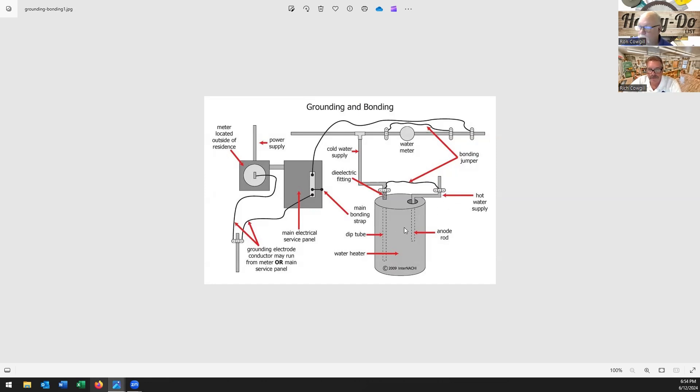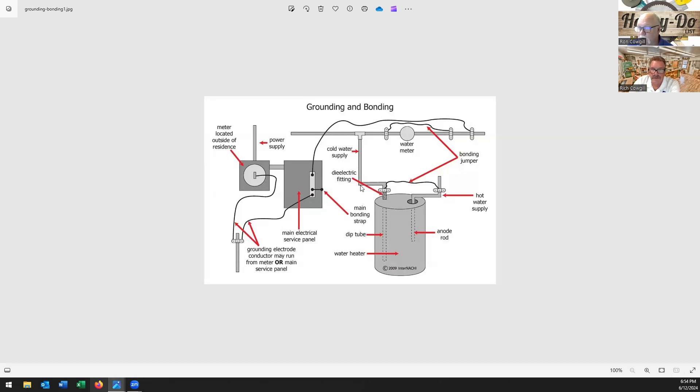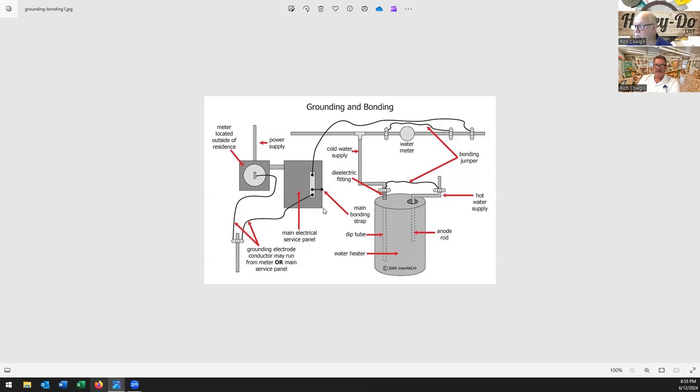Because if for some reason you drain that out and now you don't have the water to be able to complete that connection. I guess the one thing that's missing here is if this is a gas water heater, they also require you to go from one side, one pipe, down to the gas pipe also. Yeah, I didn't find - I could not find any that actually showed the gas pipe, but yes, you want to bond your gas pipe. So these are fairly important here that you got to watch out for this one, and then you should have one more that goes down to the gas if you've got a gas water heater. And that way you're tying all that together and you're eliminating all those potentials and differences there.